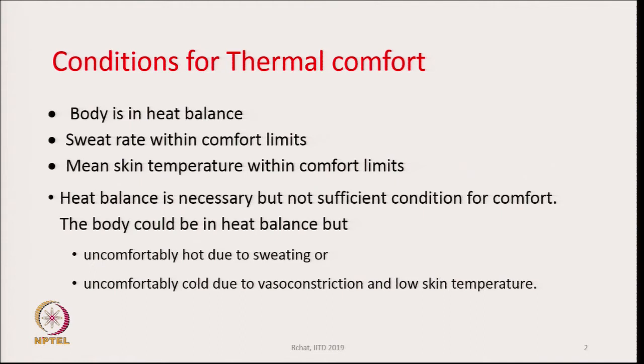Heat balance is necessary but not sufficient condition for comfort. This is a very important statement: balance is definitely necessary but not sufficient. The body could be in heat balance but uncomfortably hot due to sweating — if too much sweat is generated we will not feel comfortable — or it could be uncomfortably cold due to vasoconstriction and low skin temperature.